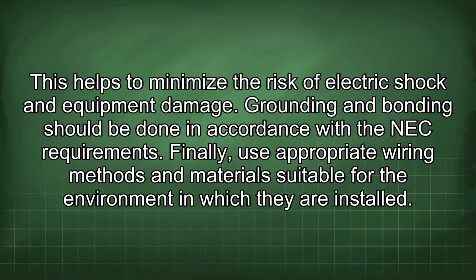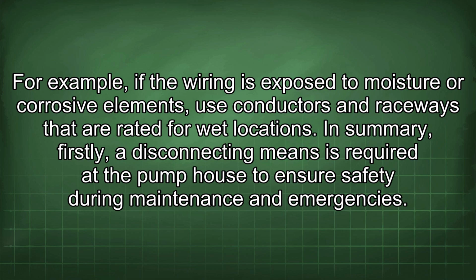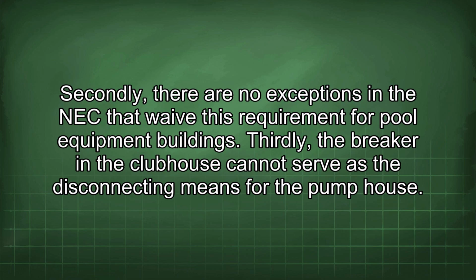Finally, use appropriate wiring methods and materials suitable for the environment in which they are installed. For example, if the wiring is exposed to moisture or corrosive elements, use conductors and raceways that are rated for wet locations. In summary, firstly, a disconnecting means is required at the pump house to ensure safety during maintenance and emergencies. Secondly, there are no exceptions in the NEC that waive this requirement for pool equipment buildings. Thirdly, the breaker in the clubhouse cannot serve as the disconnecting means for the pump house.